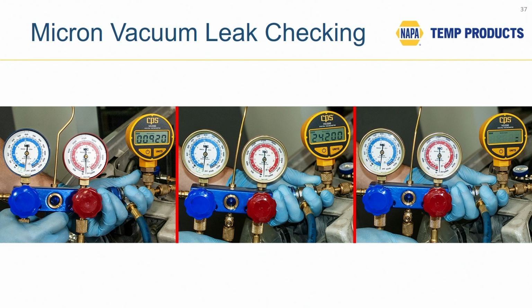Just looking at the low side gauge, the regular blue manifold gauge set, the needle looks pinned at 30 inches, right? And you can see that the micron gauge is at about 920 microns. Now, an ideal textbook vacuum on a deep vacuum system would be about 500 microns or less, but for this conversation, let's go with 920. After 10 minutes, you can see that the micron level is 24,000. It's gone from 900 to 24,000, but look at the blue gauge. The needle is still pinned. It looks like it's pulling.